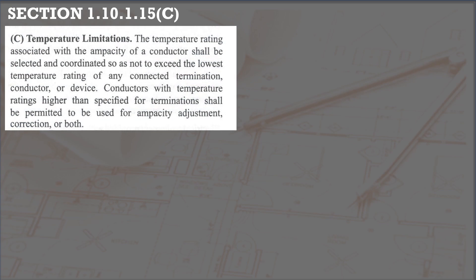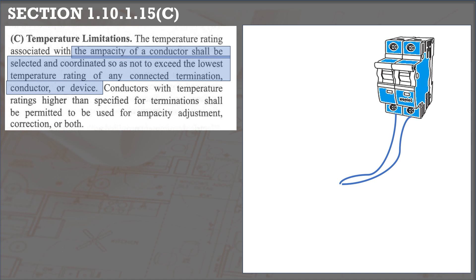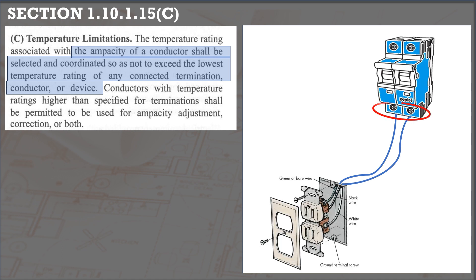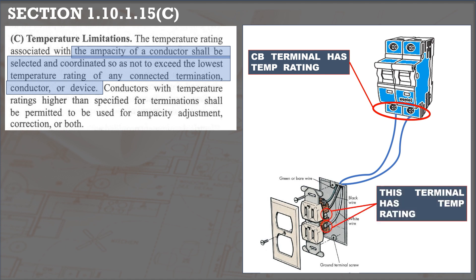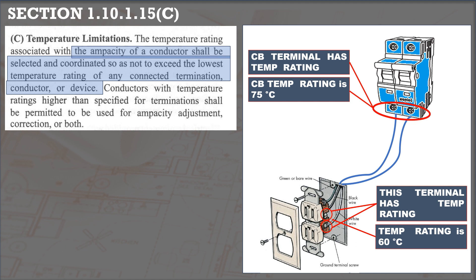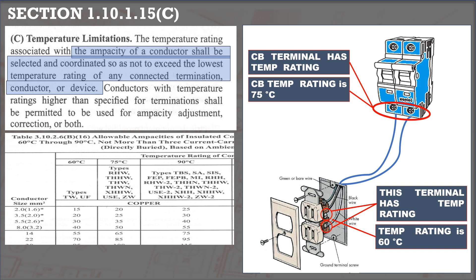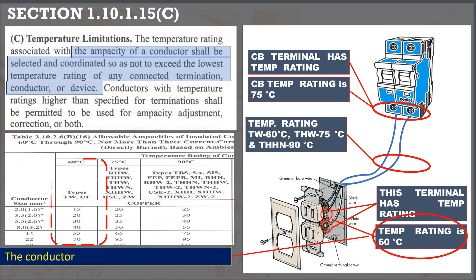Section 1.10.1.15C states that the ampacity of the conductor will be based on the temperature rating of the lowest-rated connected termination, conductor, or device within the equipment served. In the figure shown, a conductor is terminated to a circuit breaker and a receptacle outlet. If the circuit breaker terminal has a temperature rating of 75 degrees Celsius and the receptacle outlet is 60 degrees, the termination point with the lowest temperature rating is the determining factor. Hence, whether we use THW or THHN, the conductor's ampacity will be based on 60 degrees Celsius.